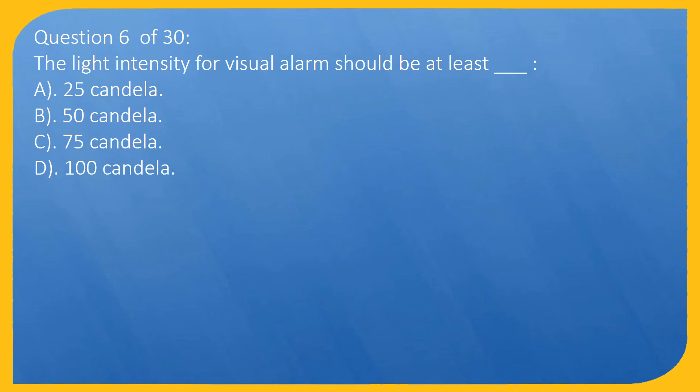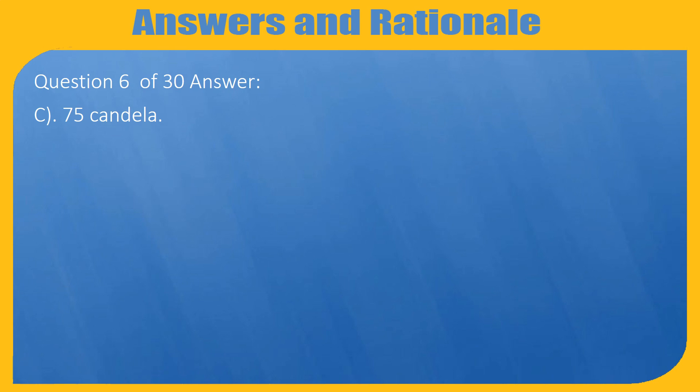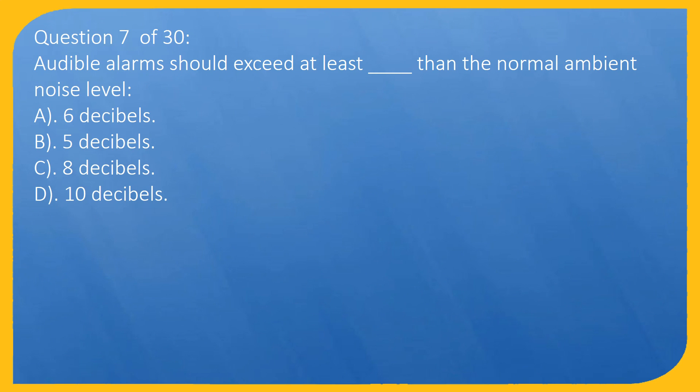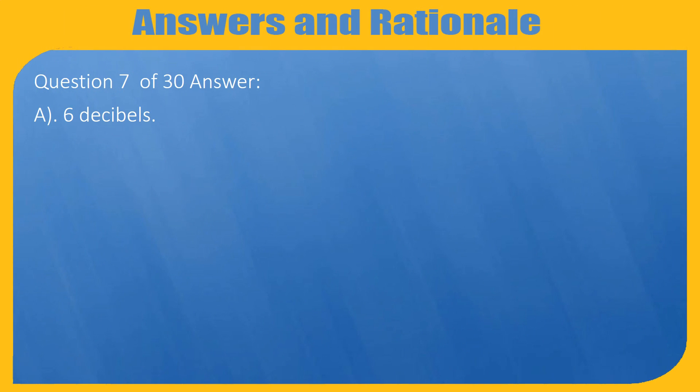Question 6 of 30: The light intensity for visual alarm should be at least: A. 25 candela, B. 50 candela, C. 75 candela, D. 100 candela. Answer: C. 75 candela. Question 7 of 30: Audible alarms should exceed at least how much more than the normal ambient noise level? A. 6 decibels, B. 5 decibels, C. 8 decibels, D. 10 decibels. Answer: A. 6 decibels.